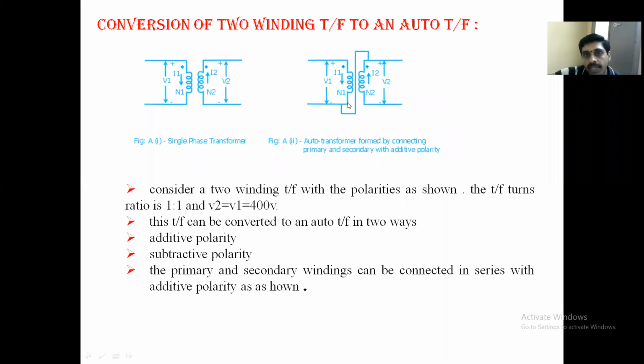You can observe the secondary is connected in series with the primary. Here the polarities are very important, which I will show you in the next picture. It can be converted to an auto transformer in two ways: additive polarity and subtractive polarity. Additive depends upon the dot convention. If you connect in this direction, it is additive polarity. If you connect in the opposite direction, the polarity is subtractive. Primary and secondary windings can be connected in series with additive polarity as shown here, in the direction of current.